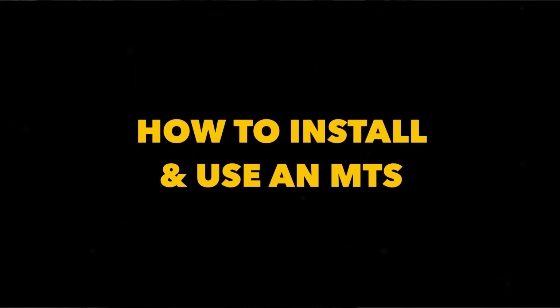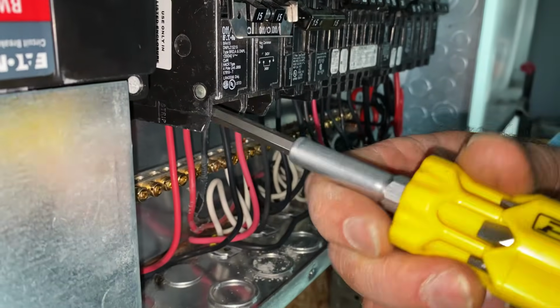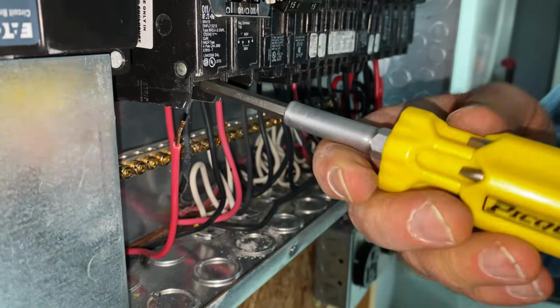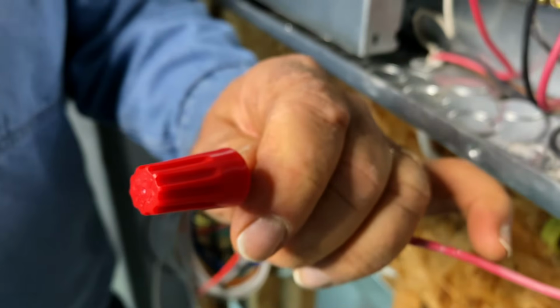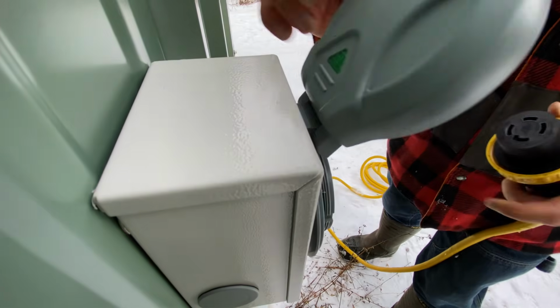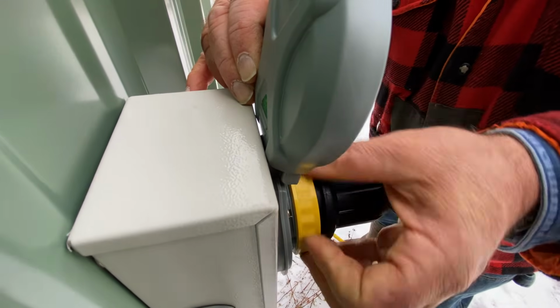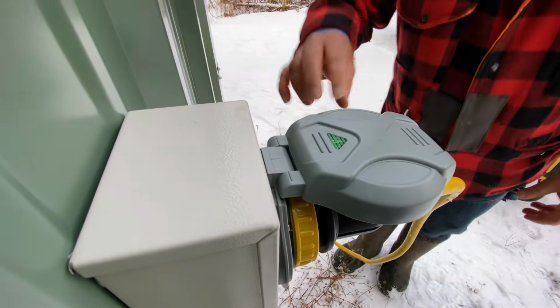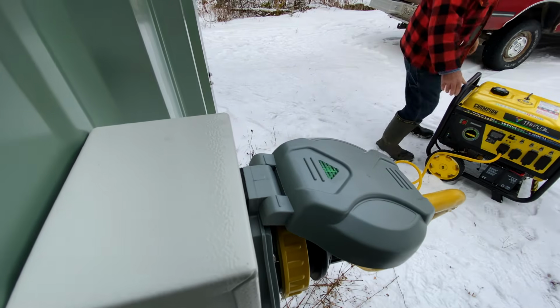How to install and use an MTS. Installing a transfer switch is work for a licensed electrician, but the concept behind the product is simple. As a homeowner, you'd be wise to understand what's involved before hiring anyone. Wires connected to circuit breakers in your existing electrical panel get disconnected and rerouted to different breakers within the transfer switch panel itself, typically located nearby. These new connections involve short lengths of cable extending to the transfer switch with twist-on wire nuts securing the connections to existing household wiring within your electrical panel. A weatherproof outlet comes with most transfer switch kits, including the Champion unit I have at my place, and gets installed on the outside of an exterior wall to allow easy connection of the generator.